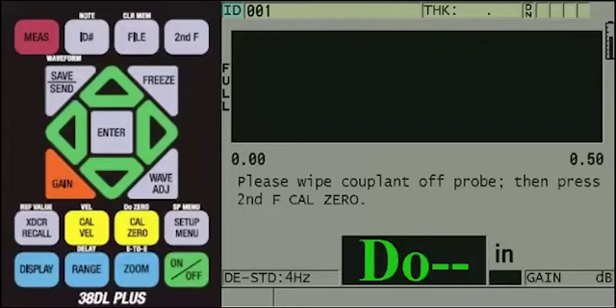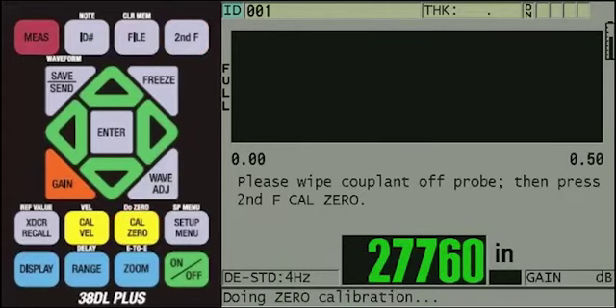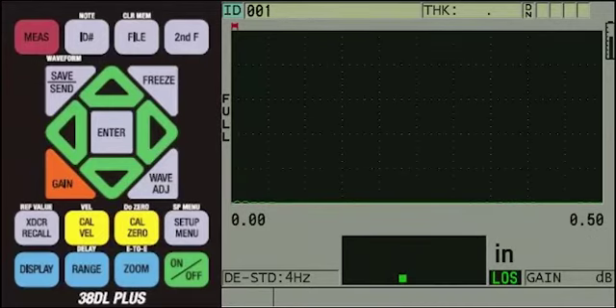Once the gauge powers on, it will prompt the user to perform a Do Zero. Make sure there is no couplant on the end of the transducer. You can then press and release the second F key first, and then press the yellow Cal Zero key. Once this process is completed, the measurement screen on the instrument will be displayed.